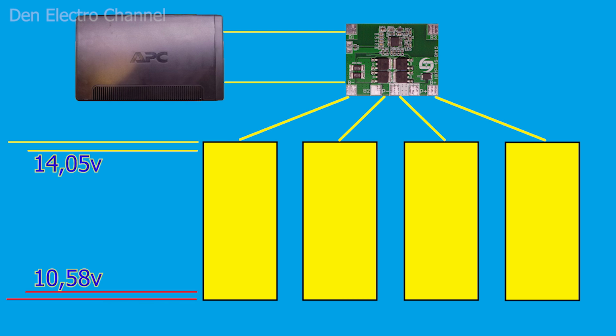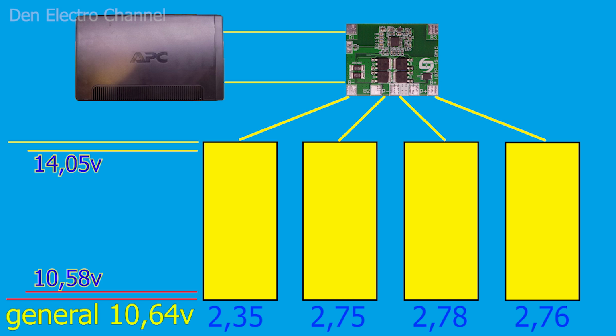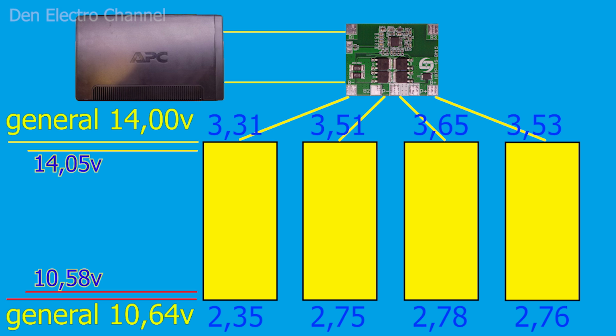If the worst-case scenario happens and one of the batteries discharges much faster than the others, and their total voltage is still more than 10.6 volts, then the BMS will turn off. The same situation may also occur when charging: if the voltage of the batteries is very skewed and one of them is the fastest to reach maximum voltage, the BMS board will disconnect the batteries from the circuit. The protection built into the uninterruptible power supply won't have time to act, since the total voltage hasn't reached its required limits.